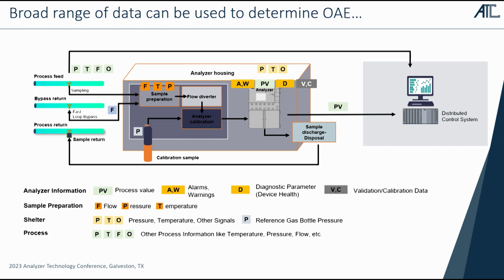But if you look into other information, there are a lot of possibilities. Of course, the validation and calibration results. You can get information from the shelter environment, for example the temperature and the pressure. You can get information out of sample preparation systems, if they are smart, providing pressure, temperature, flow. You can even get information about the pressure in the reference gas bottle if you have a sensor there. And you can get some diagnostic information out of every device, which we will see on the next pages, which you normally use if you're doing troubleshooting.